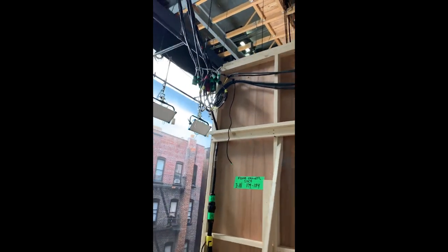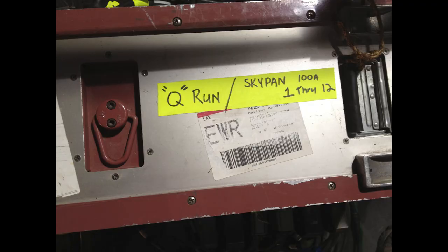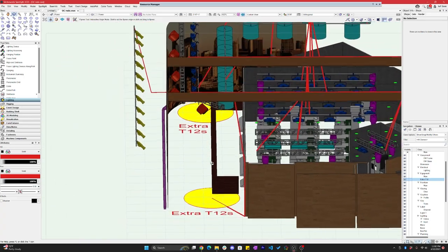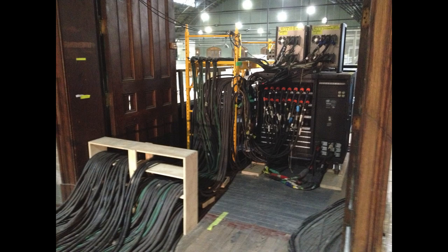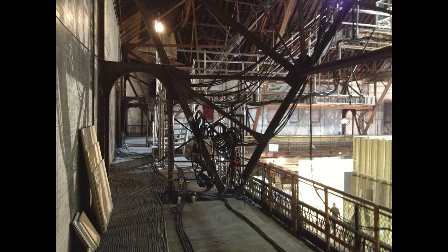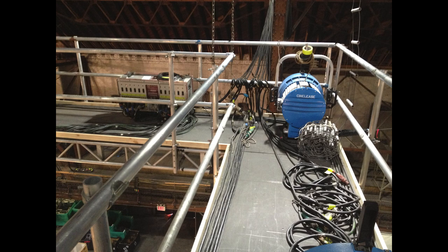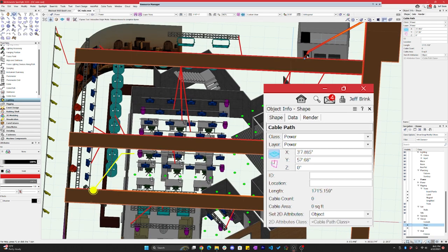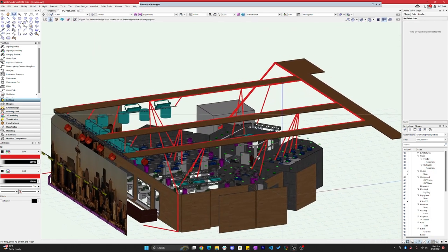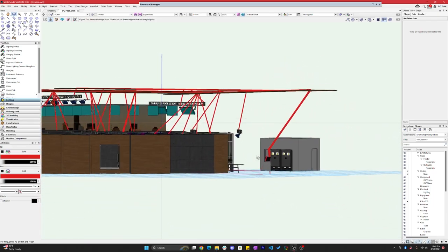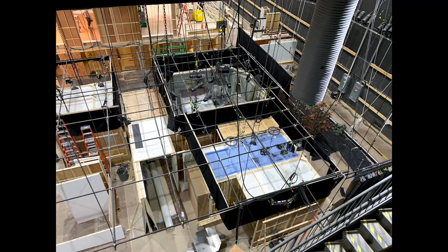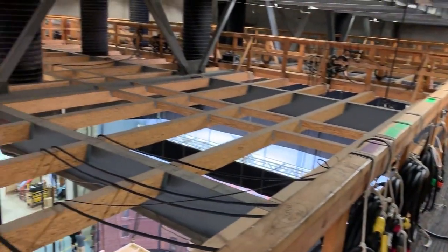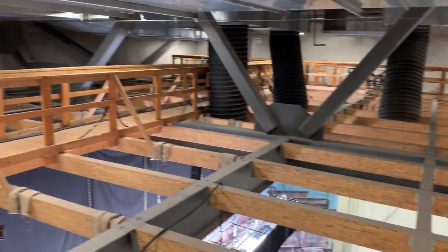Furthermore, for all of your T12s, you'd need to run separate 100-amp runs to your truss of T12s, and then to the corners of the set for plugging in any you need to add along the ground. It's one long cable run from the dimmer room to a point in the stage, times however many lines you need to put there. That's a lot of long cable runs, easily 100 to 200 feet. And it honestly takes forever to install because you're going up in a lift, crossing over to the grid, throwing it to the other side, moving the lift for each run of cable. It's a lot of work.